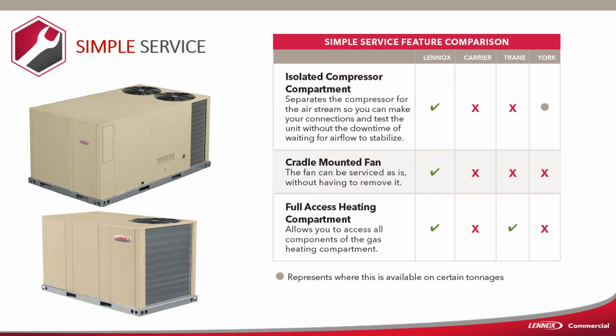Has an isolated compressor compartment, which separates the compressor from the air system around the evaporator, or excuse me, the condenser coil. This allows you to put your gauges on there and leave that door open while you're working on the unit without worrying about getting false readings because the air is bypassing the condenser coil.